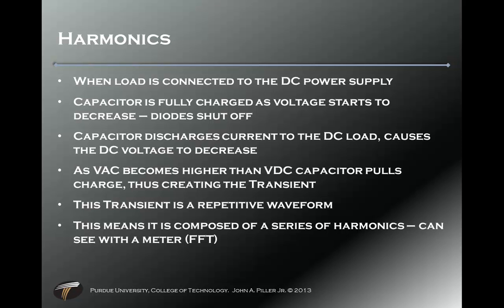So where does this come from? When a load is connected to the DC power supply, the capacitor gets fully charged; as the voltage starts to decrease, the diodes shut off. The capacitor then discharges current to the DC load and the DC voltage decreases. As VAC swings back to the positive, it becomes higher than the DC voltage, the capacitor pulls in charge and creates a transient. That transient becomes a repetitive function — every 60 hertz. That repetitiveness means there are harmonics, and we can see the series of harmonics with an FFT meter, or do the math as discussed in Lecture 4A.